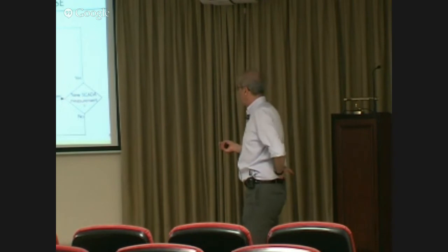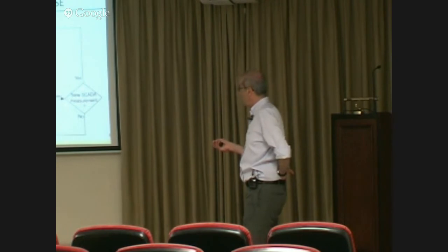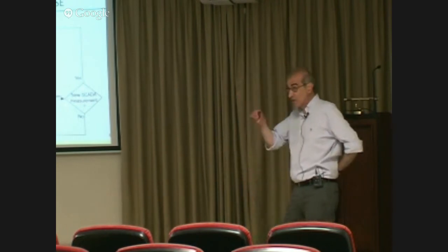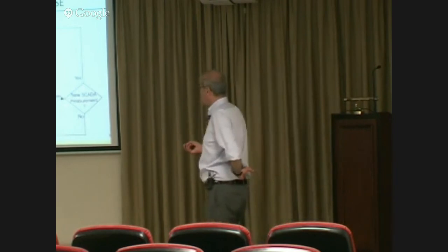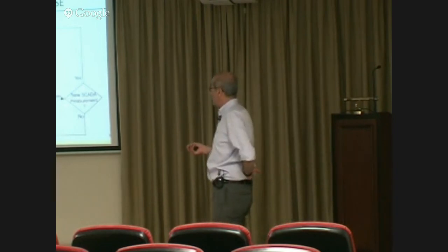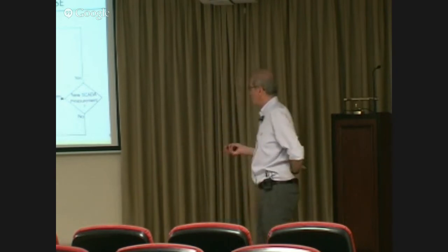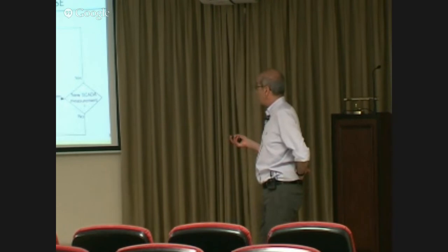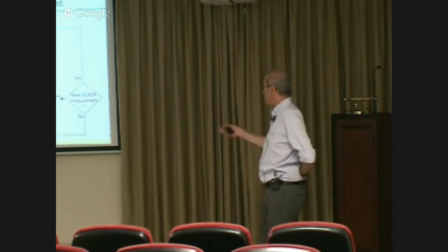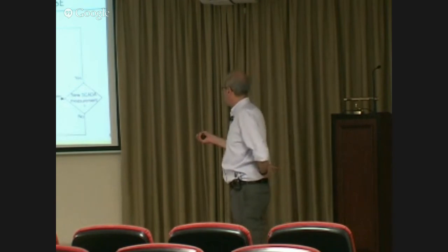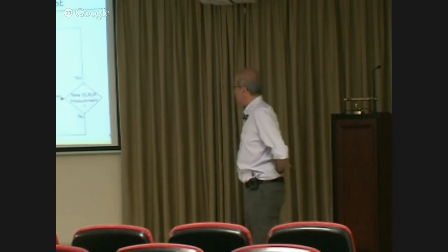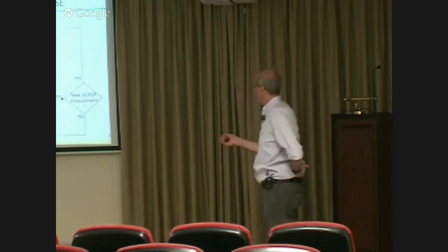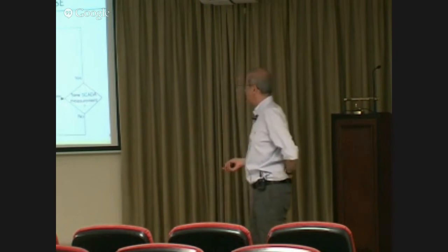If there is none, you go back, and now using this updated state, you update the SCADA measurements. You can actually calculate SCADA measurements. So those that you received in the previous scan will get updated. Not all of them, but some of them will get updated. And with these updated SCADA and the new set of PMU measurements, you do another update. You continue these updates in this period between the two SCADA scans. And then when the new SCADA arrives, you go back and, of course, start from scratch, and you build your weighted least squares estimator again with the SCADA.